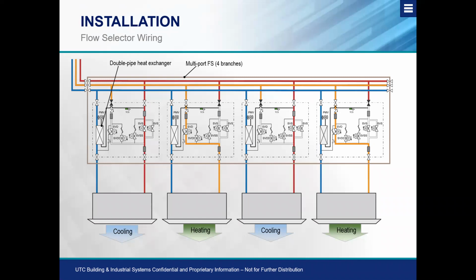So it all depends on if we have that simultaneous call. If we're all calling for heating, or we're all calling for cooling, we're really not doing much heat recovery. But when we have the simultaneous call, that's where the efficiency and the logic and the brains of these systems come into play with operating and controlling the solenoid valves.